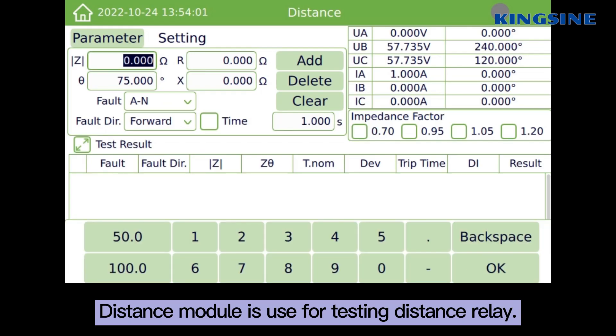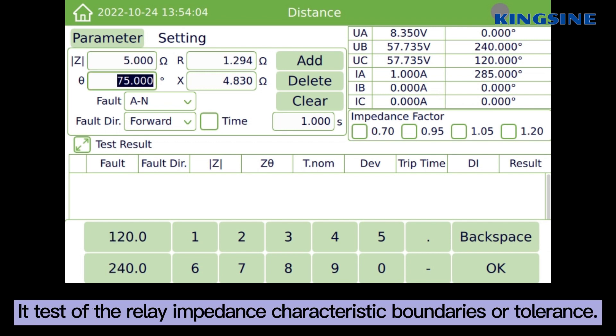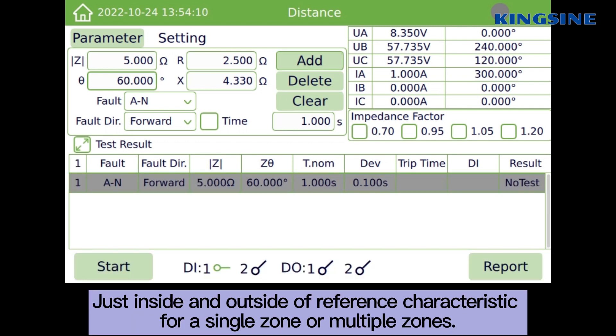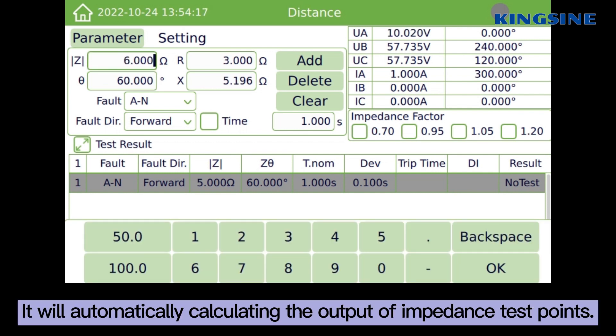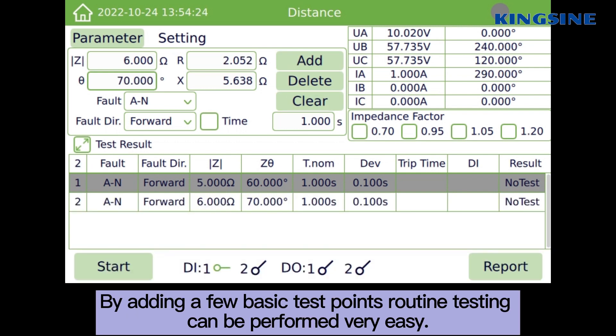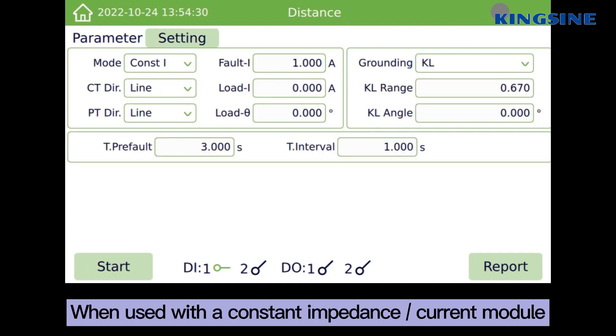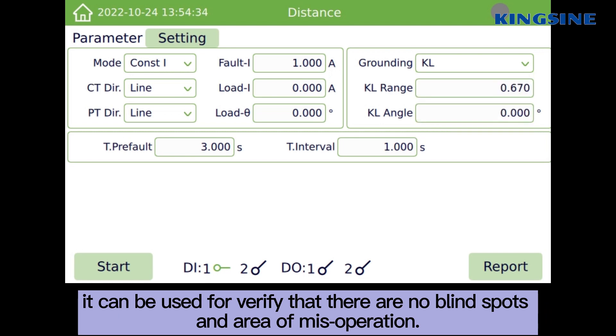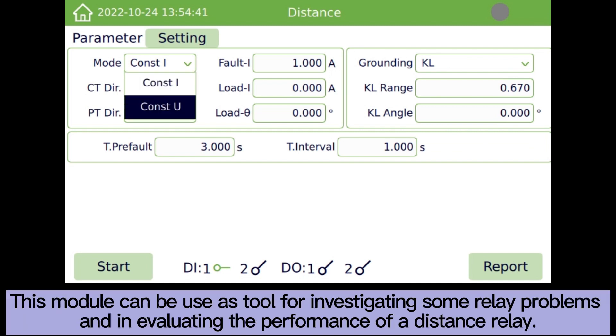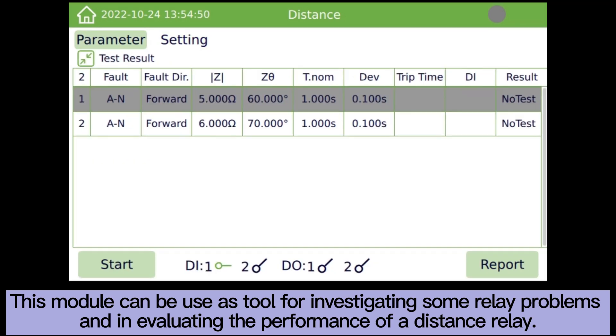The distance module is used for testing distance relays. It tests the relay impedance characteristic boundaries or contours, just inside and outside of the reference characteristic. For a single zone or multiple zones, it will automatically calculate the output of impedance test points. By adding a few basic test points, routine testing can be performed very easily. When used with the constant impedance current module, it can verify that there are no blind spots or areas of misoperation, and can be used as a tool for investigating relay problems and evaluating the performance of the distance relay.